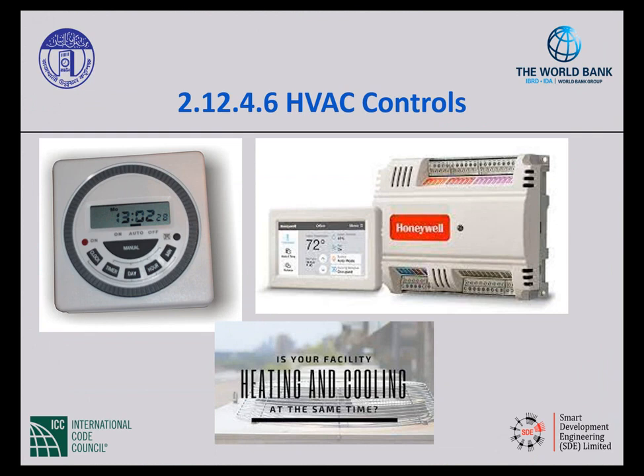For controls, it goes further. I always say the mechanical code has control issues, right? It's not going to override whatever the mechanical code itself says, but the energy portion for HVAC is telling us, okay, you have to run these systems, but let's provide controls to run them as little as we possibly can, or as efficiently as we possibly can. So we're not going to tell you you can't run your systems. We're just going to ask you to shut them down when they're not needed or turn them down a little bit whenever you can. That's what we're looking at. So a lot of the HVAC requirements when it comes to energy efficiency have to do with controls.